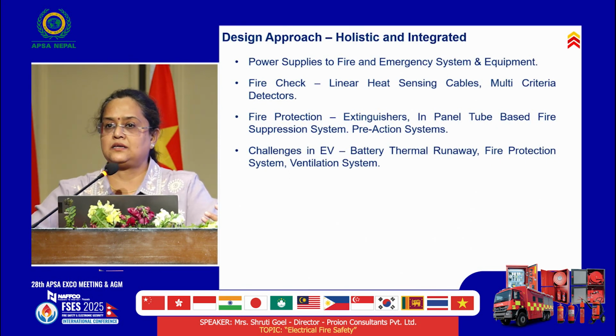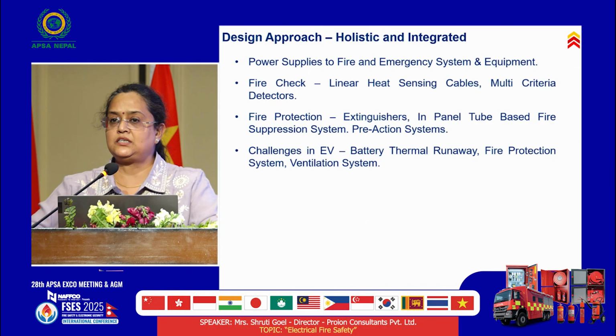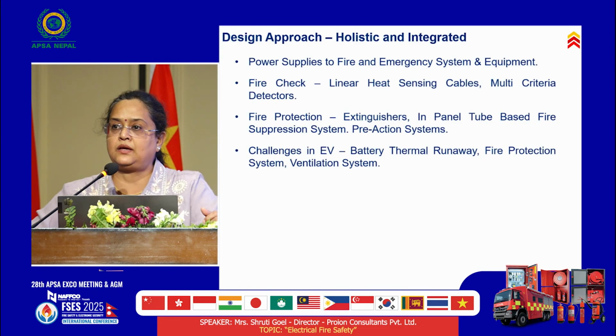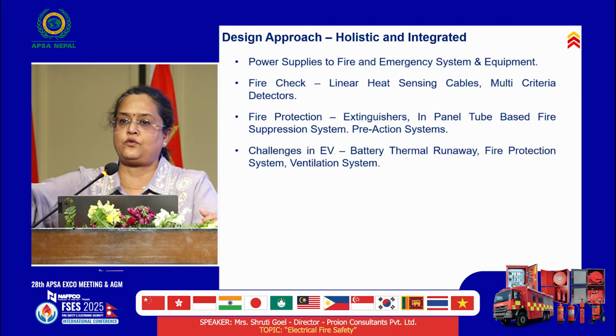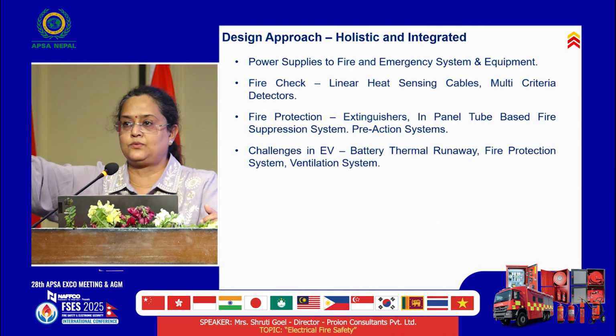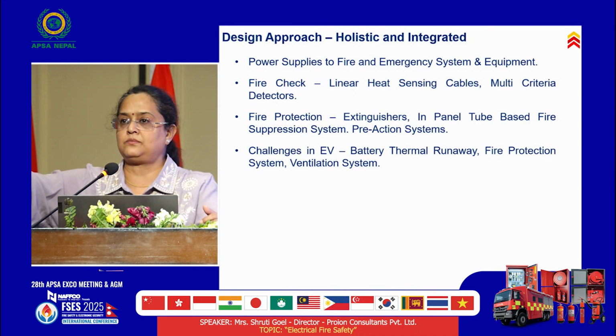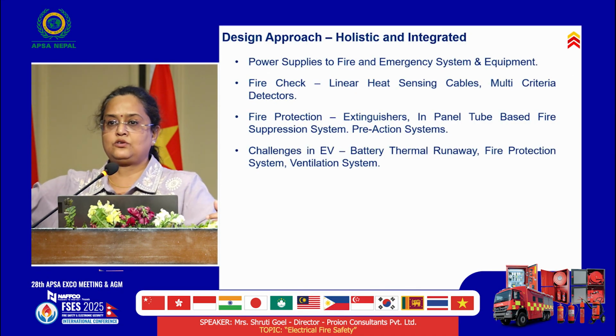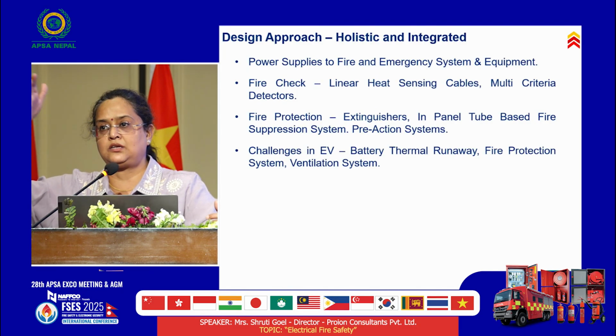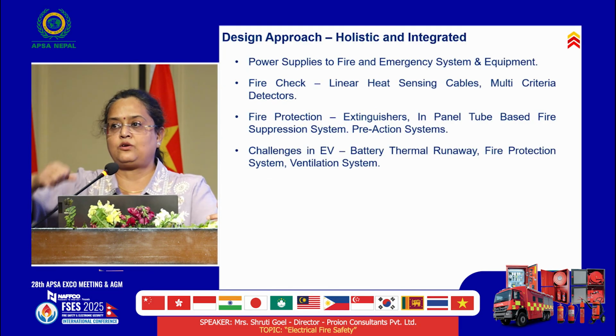So lights, emergency lights, fire alarm system, evacuation system, ventilation system, there are so many things which have to remain on even during emergency. It should not happen that somebody just comes and switches off the entire system and nothing is working. So there are sets of systems you have to design in parallel so that they keep getting electricity even though somebody is trying to switch them off.